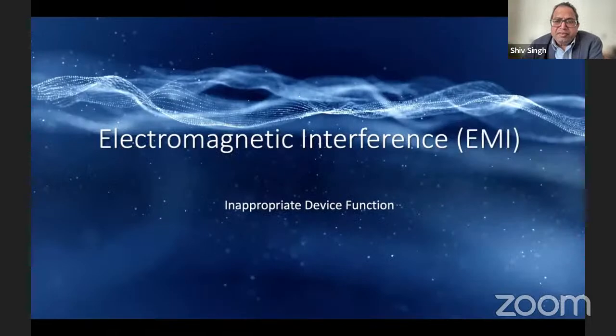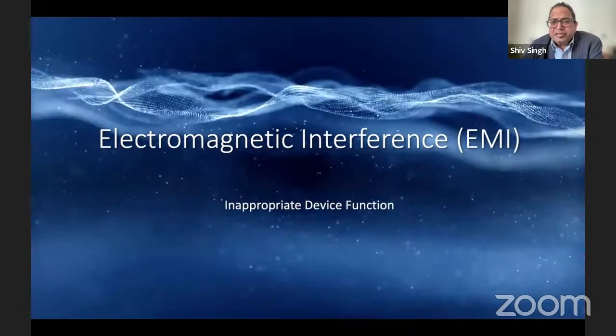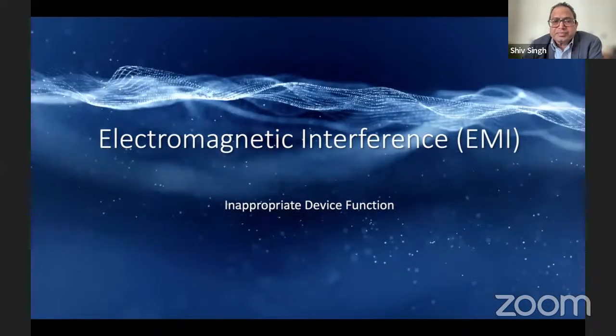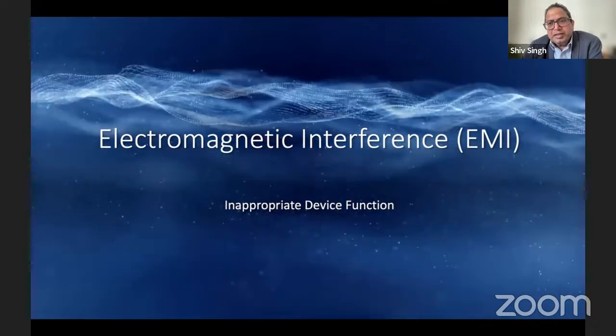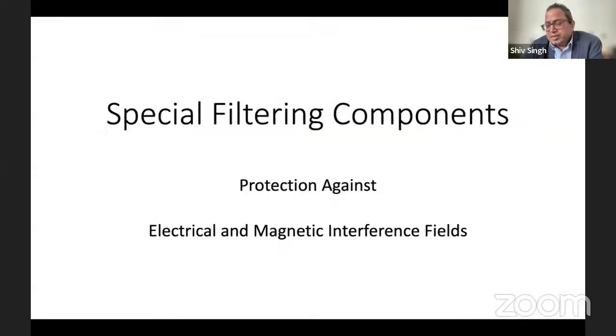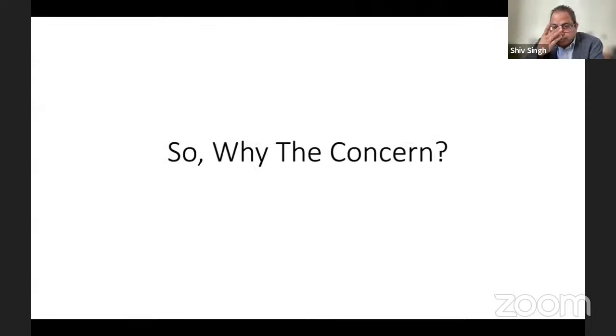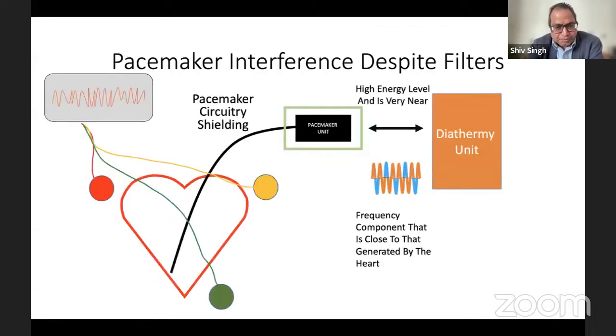One of the most important interferences which can happen is the electromagnetic interference from the diathermy, which can lead to inappropriate device function. So there are special filtering components within the pacemaker. There is better shielding, there's protection against that, but still they can happen. And why is this a concern? Pacemaker interference can occur despite the filters, and this can happen because the diathermy is kept very close to the pacemaker unit. The pacemaker is on the left side of the patient, infraclavicular, and the diathermy is very close to it. You're using very high frequency, high current, and this can cause radio frequency interference even despite having good shielding. The shielding is for the pacemaker unit itself, but interference can happen through the lead.